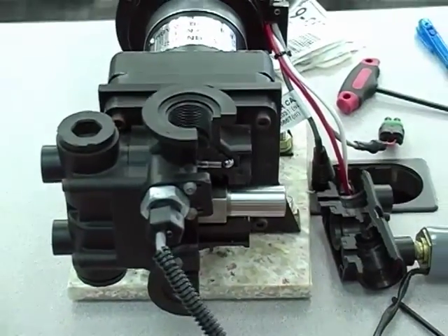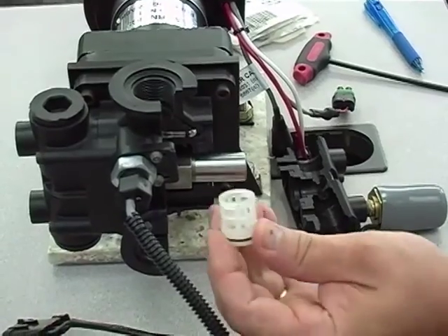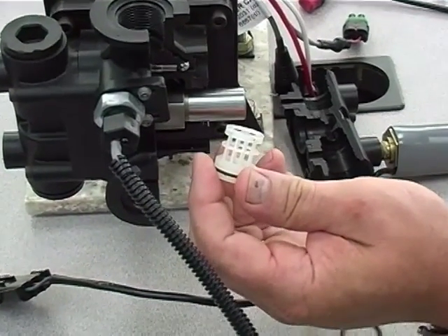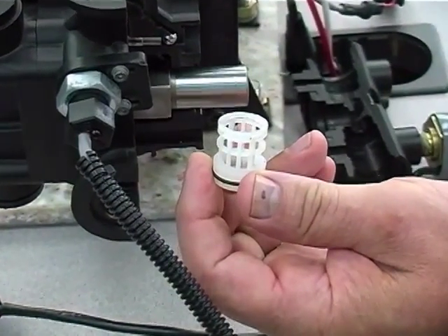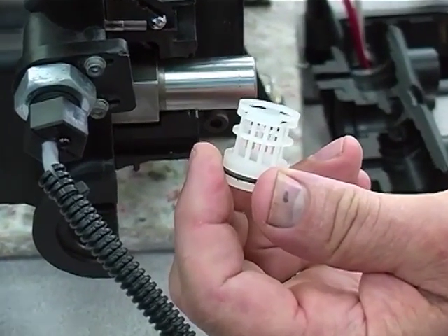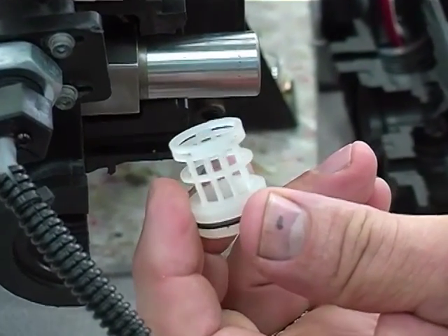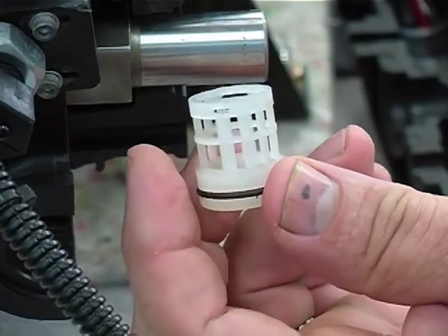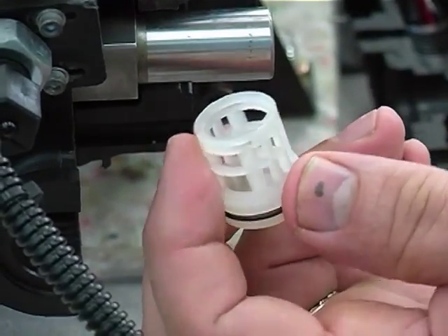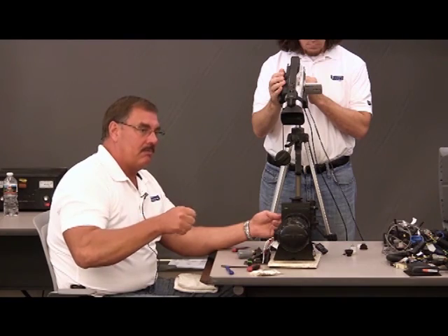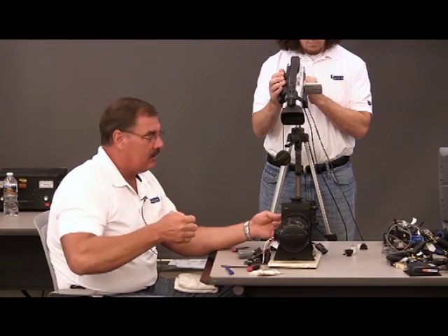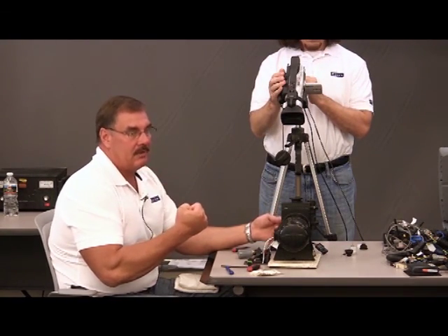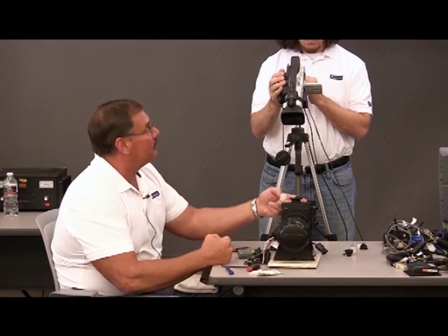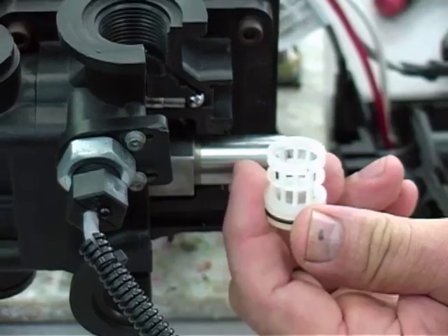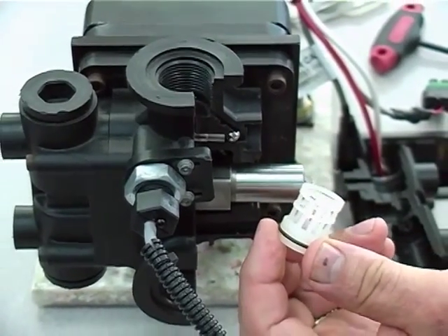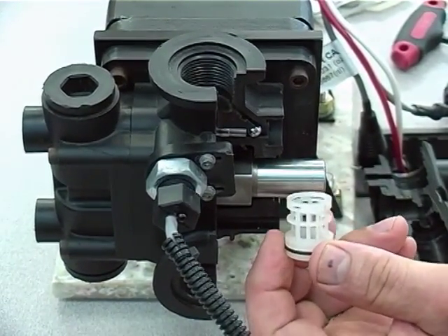I'm going to backtrack here just quickly on these check valves. They are made out of a component called Kynar. It's a plastic makeup, but it's much harder and chemical resistant. We used to make them stainless steel. I think one of the reasons we went to the Kynar is if someone would deadhead their pump, if you try to run the pump with the valve shut and you're trying to force chemical out of there, you could actually crack the head of the pump. This way, what usually happens is the valve itself will crush and allow chemical to go through, so it's more of a stop.